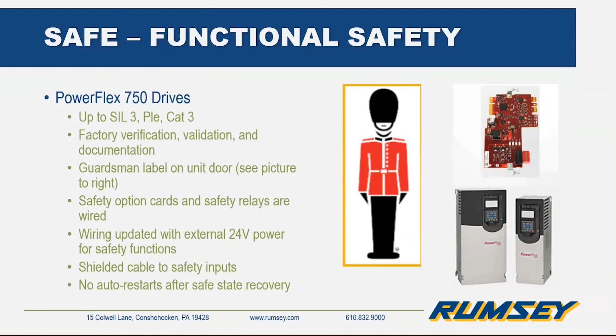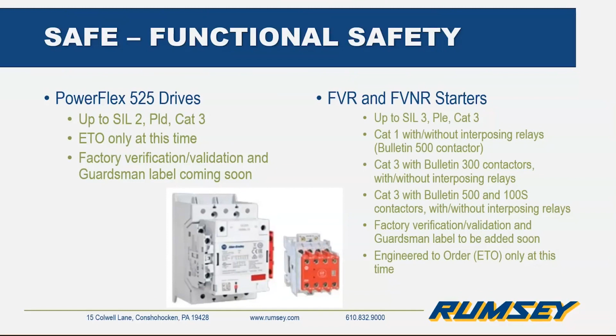So 2 other MCC unit types that can incorporate functional safety are PowerFlex 525 drives and full voltage non-reversing starter units. This is again achieved by using certain safety components such as safety relays and contactors. And although they are available to order right now, these unit types are not really as developed as the PowerFlex 750 drives. As of right now, they are ETO only, which is engineered to order, and they lack the factory validation and Guardsman logo, but Rockwell is working on that, and they hope to be done with these soon.